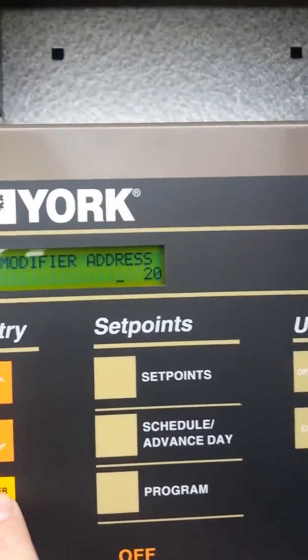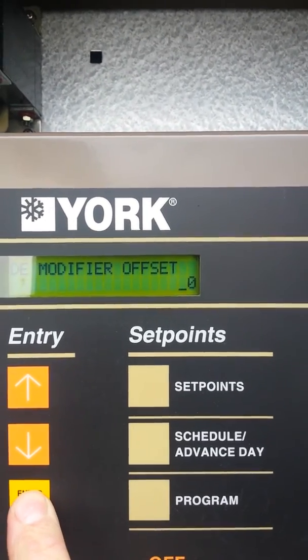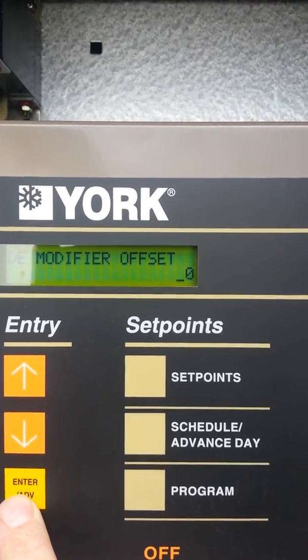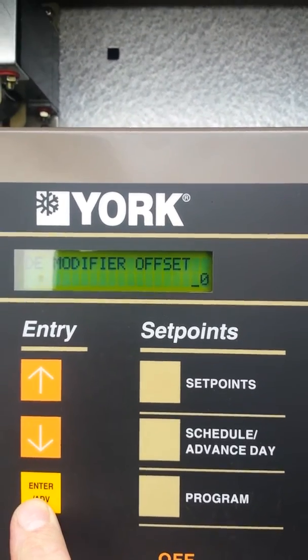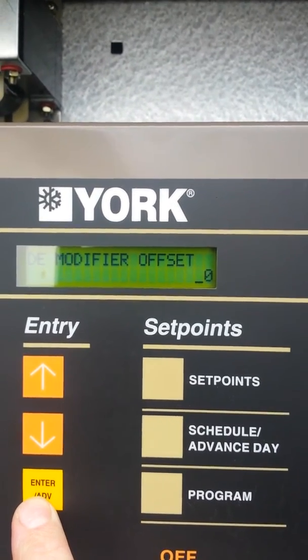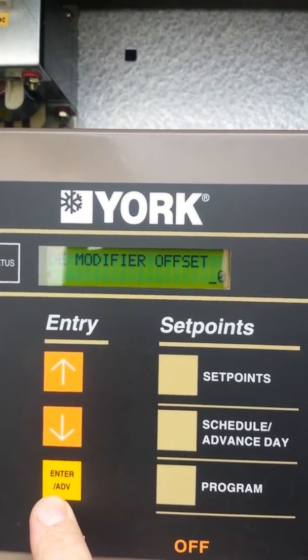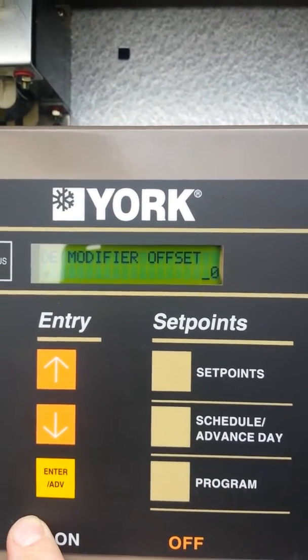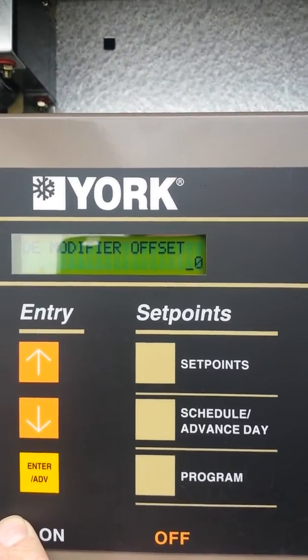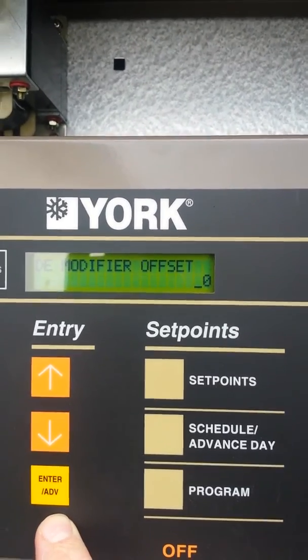As we make our way through, we go to the next stage: the modifier offset. This number can go from zero to 99. So if you had 99 more devices you wanted to put in the 2000s, you can do it here. This unit might be 2000, and then if you had two or three more chillers, you can make the next chiller 2001 and the next one 2002. That's how you would do that.